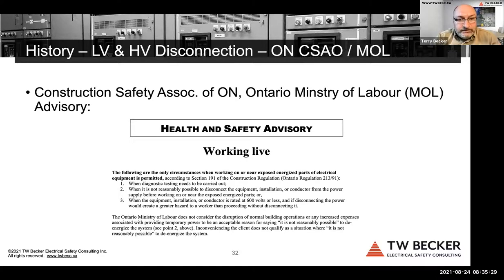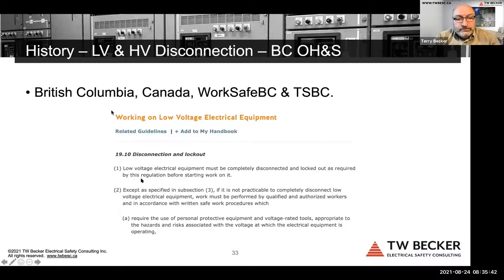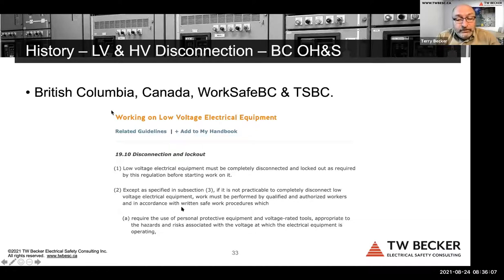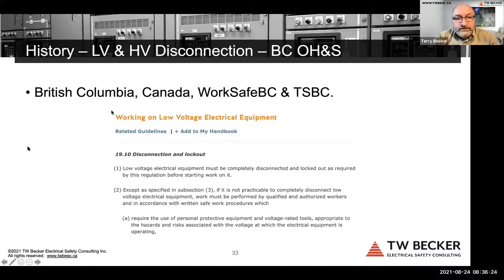WorkSafe BC OH&S regulation rule 19.10 states low voltage electrical equipment must be completely disconnected and locked out before working on it — but you must read the rest of the rule. Subsection 3 states: if it's not practicable to completely disconnect, work must be performed by qualified and authorized workers in accordance with written safe work procedures requiring PPE and voltage-rated tools appropriate to the voltage at which the equipment is operating. You must read regulations and interpret them appropriately, and through an electrical safety program with a defined risk assessment procedure, the employer takes control.